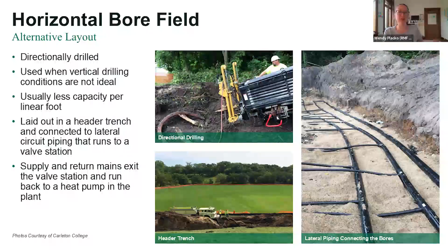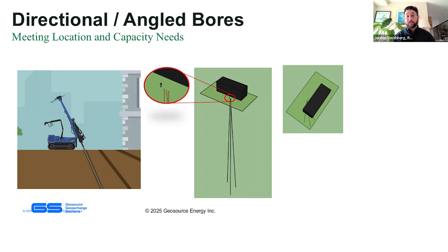All right, let's talk directional. This was a really interesting presentation on another technology: if you don't have a large open field to drill in where you'd space out these wells, typically 15 to 25 feet apart when going straight vertical, there are angled options. You basically start at the same point at the surface, and by angling out the bores, you still achieve a very high level of heat exchange without taking up as much surface level footprint. Really exciting stuff. Canada is doing a lot of this, and it's a great option in dense areas or where you want to go underneath existing structures.